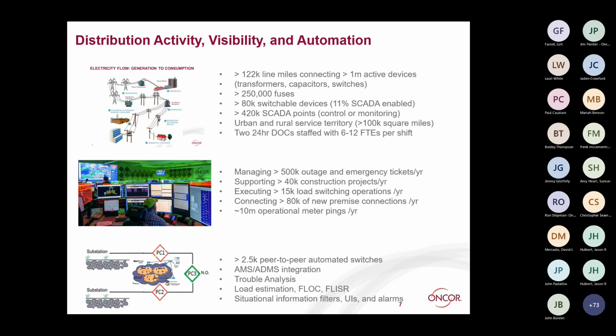Based on the pattern of those calls coming in, the software automatically interprets these calls and decides this transformer is most likely the one that's out, or this recloser, or this fuse is the one that opened to protect the system, and this is the source of the outage. So when we dispatch, we always respond to devices. We don't go to the customer, we go to where the device is located that's most likely to cause that power interruption.